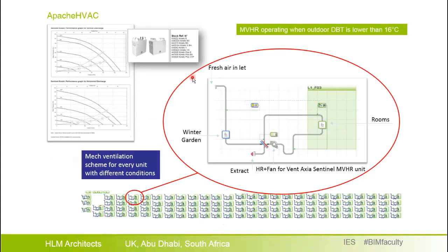Through Apache HVAC we simulate the mechanical ventilation system. We see a simple network scheme where fresh air is taken in and led to the winter garden, from there to the heat recovery unit, and then supplied to the rooms — which are multiplexed, meaning there are multiple rooms in this scheme. Exhaust air is then taken back to the heat recovery unit and exhausted outdoors.